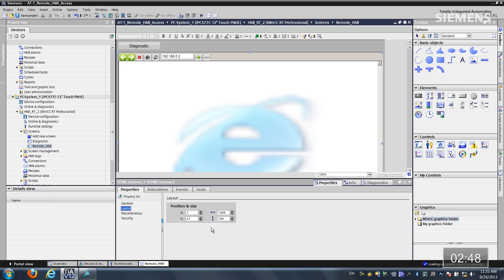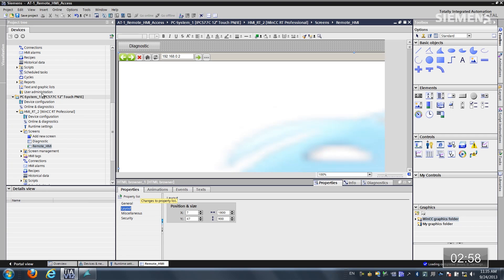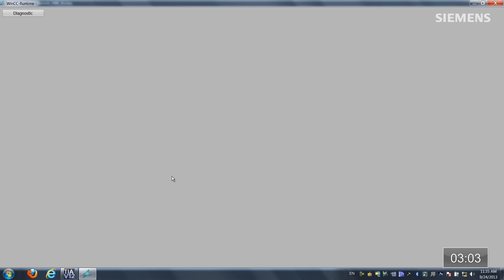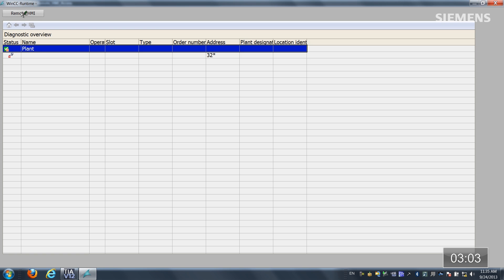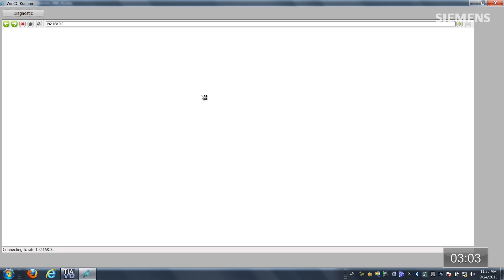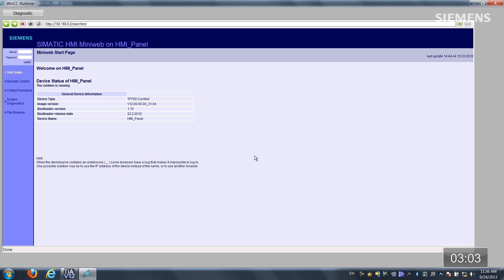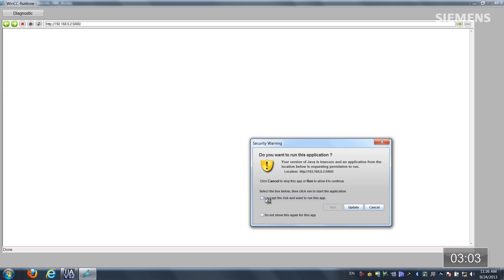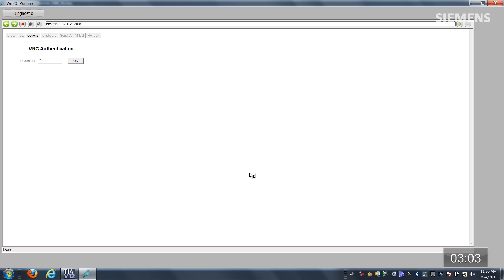To change an attribute, I'll go to Layout and set it to 1800 by 900 on the X and Y axis. Then I'll give focus to the PC system and click on compilation — it's going to compile this back into the project since the SCADA system is already running. Giving focus to it, I click the Diagnostic button and go back, then click on Remote HMI. Here is our HTML browser — it automatically finds the web server. Going to Remote Control, then Smart Client, I enable the Java Runtime, click Run, type in the password, and as you can see, I have complete control in my standard HMI architecture. I was able to do this in just a matter of minutes — now that's engineering efficiency.